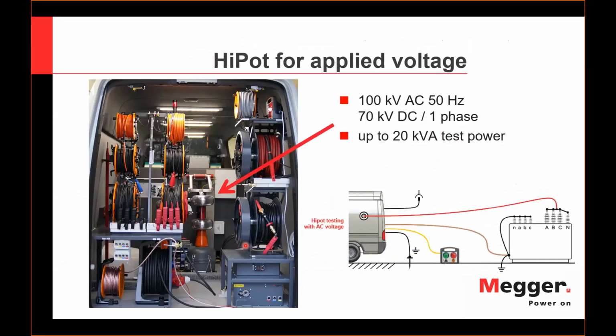Some customers also require to have a HiPot on board of the vehicle. And in that case, the vehicle gets slightly longer because we need to accommodate a single phase 100 kilovolt AC transformer, or let's say voltage source, that can output up to 20 kVA test power. And that test power can be outputted as a DC using the coax cable, or as an AC, so coated wire that would go directly to stress the HV side or LV side, while the other one is grounded.